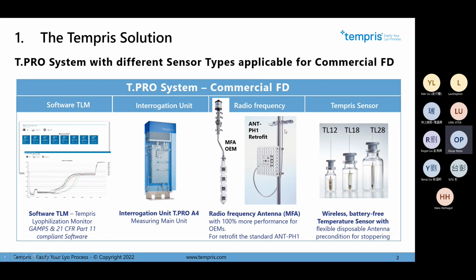The cables are covered in Teflon, which supports sterilization cycles, and the connectors are made of 316L stainless steel. The cable guides are also 316L, so everything complies with SIP and CIP cycles in freeze drying, along with the sensors we already discussed.